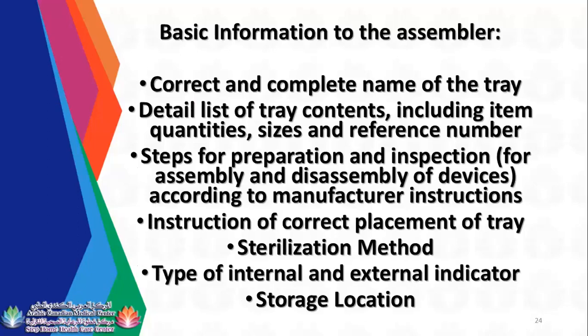So, steps for preparation, inspection, and assembly and disassembly of devices according to manufacturer instructions: correct placement of the tray, sterilization method, and type of internal and external indicator. The internal indicator should be a chemical indicator, class 5 or 6. For the external indicator, you use either indicator tape or a class 5 or 6 chemical indicator outside the rigid container, next to it, where it can be visually seen by the user when they open the package.